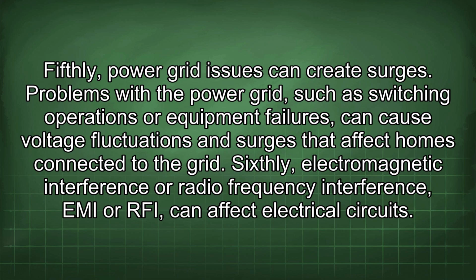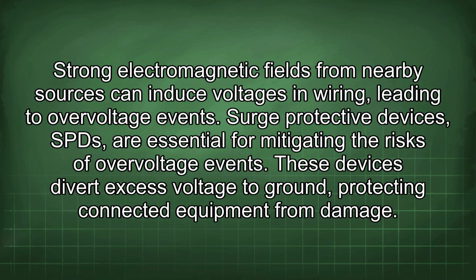Sixthly, electromagnetic interference or radio frequency interference, EMI or RFI, can affect electrical circuits. Strong electromagnetic fields from nearby sources can induce voltages in wiring, leading to overvoltage events. Surge protective devices, SPDs, are essential for mitigating the risks of overvoltage events. These devices divert excess voltage to ground, protecting connected equipment from damage.